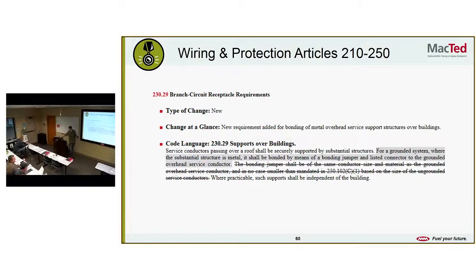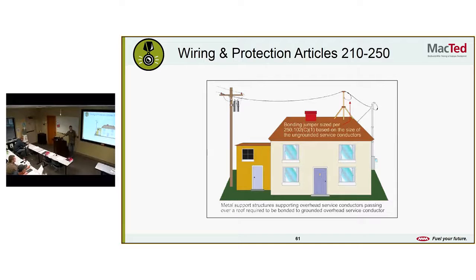Branch circuit receptacle requirements. A new requirement was added for bonding of metal overhead service support structures over buildings. So it looks like they've added, for a grounded system where the supporting structure is metal, it shall be bonded by means of a bonding jumper and listed connector to the grounded overhead service conductor. So for a metal building, you need to bond everything together. Bonding jumper size is per 250.102, based on the size of the ungrounded service conductors. So make sure you're adding bonding jumpers if you're running power to a metal building.